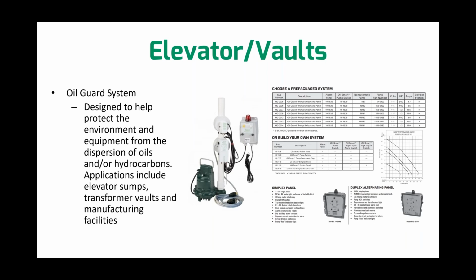This pump switch is a piggyback style switch. So the pump plugs into the back of that and then it plugs into the 115, 110 outlet. Then as the water level lowers and gets off of that longer probe, that's when the pump shuts off. Let's just say you have an application where you have a sudden inflow of water. The pump is working, but maybe it's not keeping up because all the sprinkler heads in the system have gone off for whatever reason, and now all this water is coming into the elevator shaft, if you have it tied in there, into the pit there, and the water level continues to rise. If it gets up to that higher sensor, that's the alarm sensor, and it's got 2 little probes on it, one to detect water and one to detect oil. So it'll let you know on that alarm panel what it is seeing inside the pit.